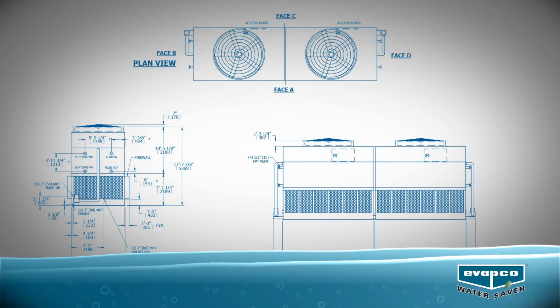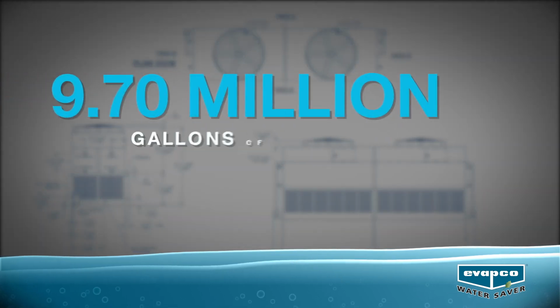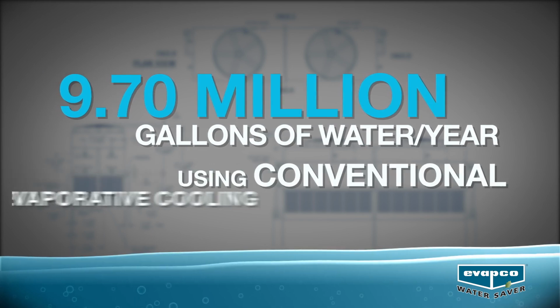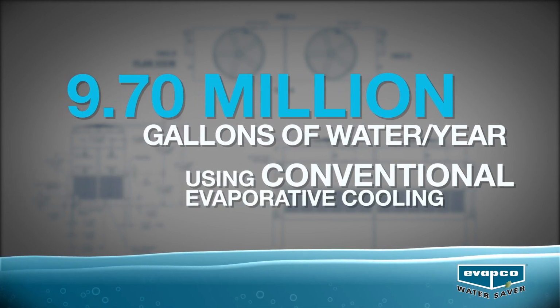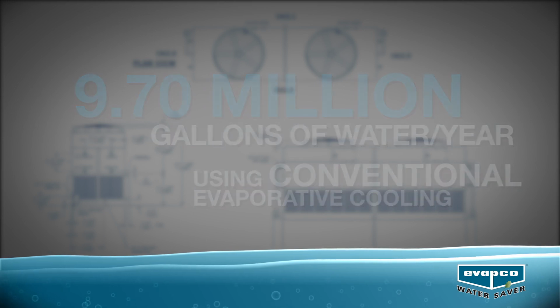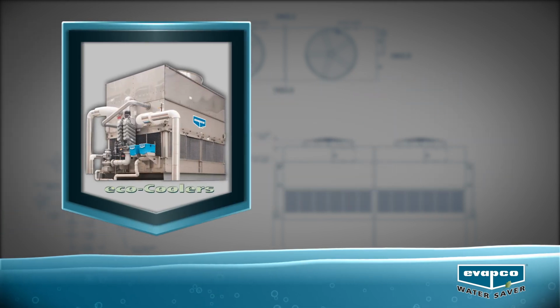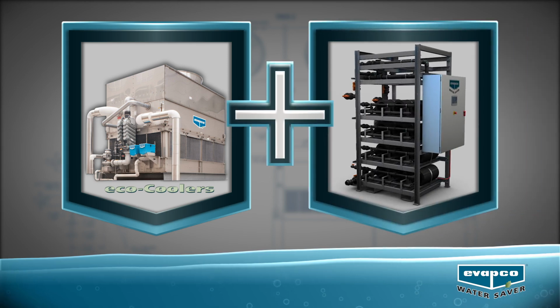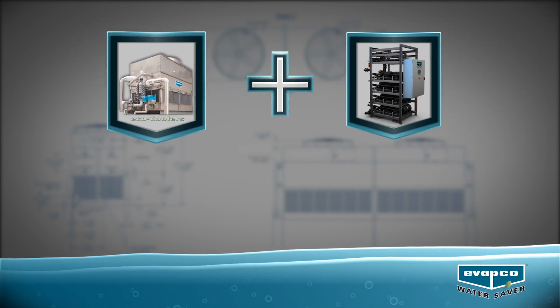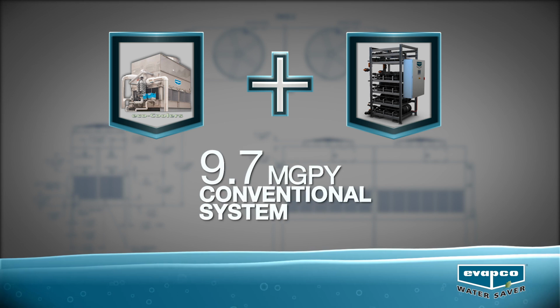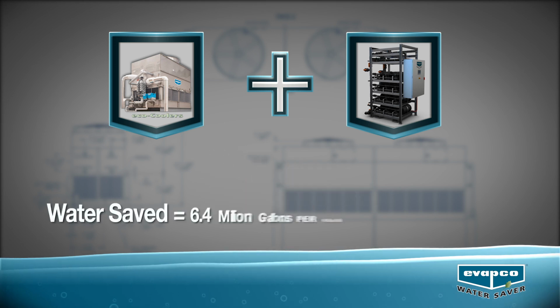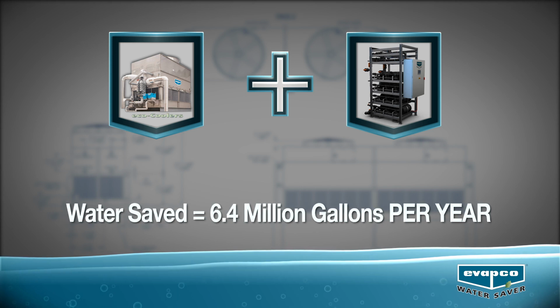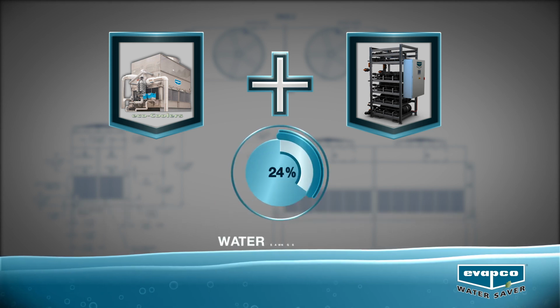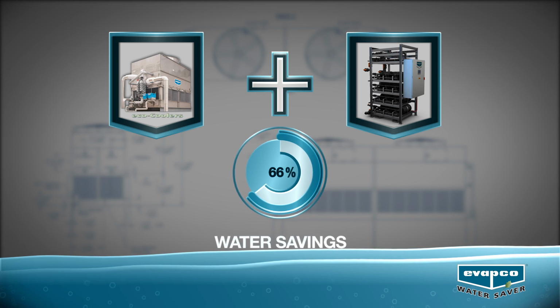of blowdown. For example, a preliminary cooling system designed for a recent data center project would have required approximately 9.7 million gallons of water per year for a conventional 100% evaporative cooling system. In an effort to save water, the engineer specified EVAPCO's eco-coolers with enhanced dry performance and an EVAPCO Water Saver to dramatically reduce cooling water usage. EVAPCO's full spectrum of water-saving technologies combined to reduce this data center's annual cooling water usage by 6.4 million gallons, which represents a 66% saving versus the preliminary design.